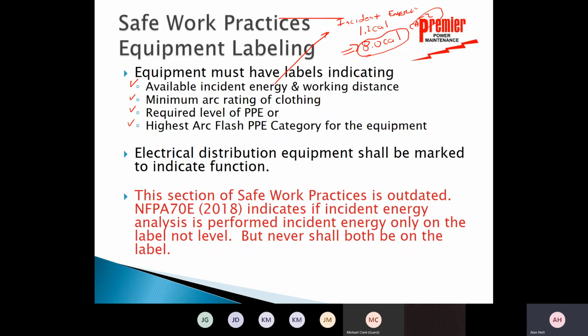Now, you would still have to have your balaclava, safety glasses, hard hat, and face shield on. And understand that that's a little outside what some people try to just tell you. But if you get above 1.2 calories, you're required, if you're working on or near, to have that balaclava, the safety glasses, face shield, and hard hat on, along with your gloves. Then our next step is if it gets above 8 calories, we're in the suit. We're in the arc flash beehive suit, and that's good up to 40 calories. So our numbers are 1.2 calorie, 8 calorie, and 40 calorie. If it gets above 40 calorie, we cannot work there.